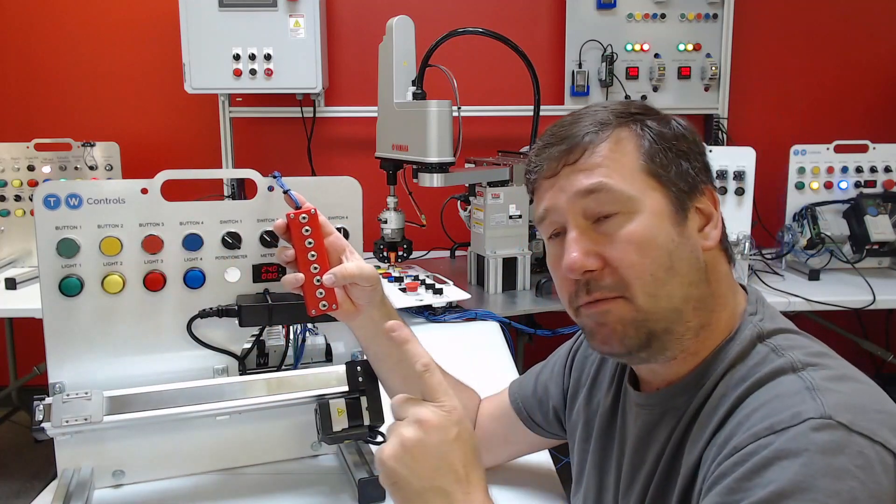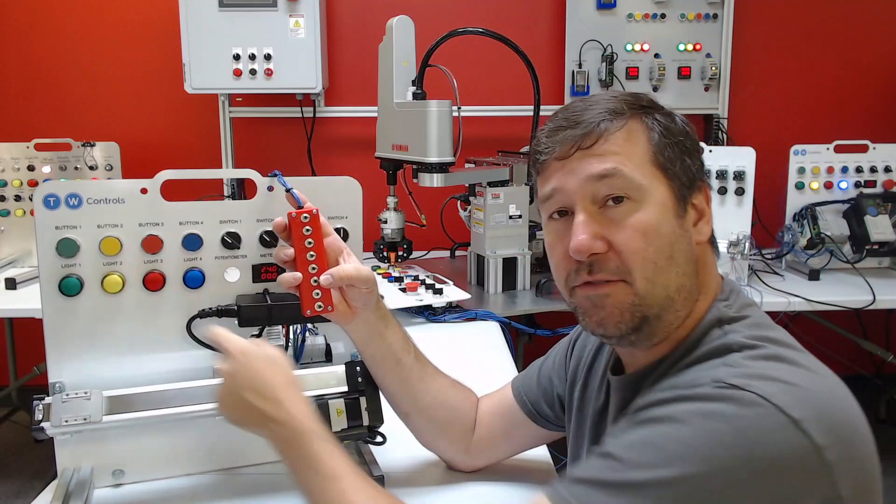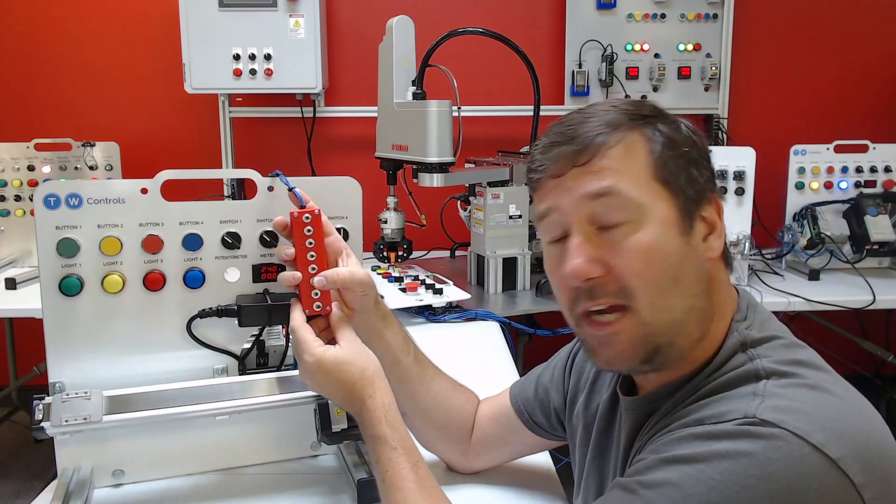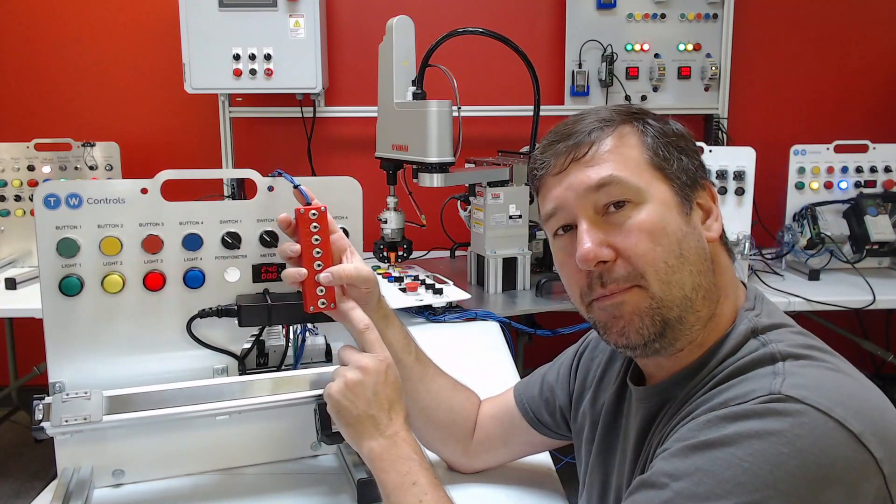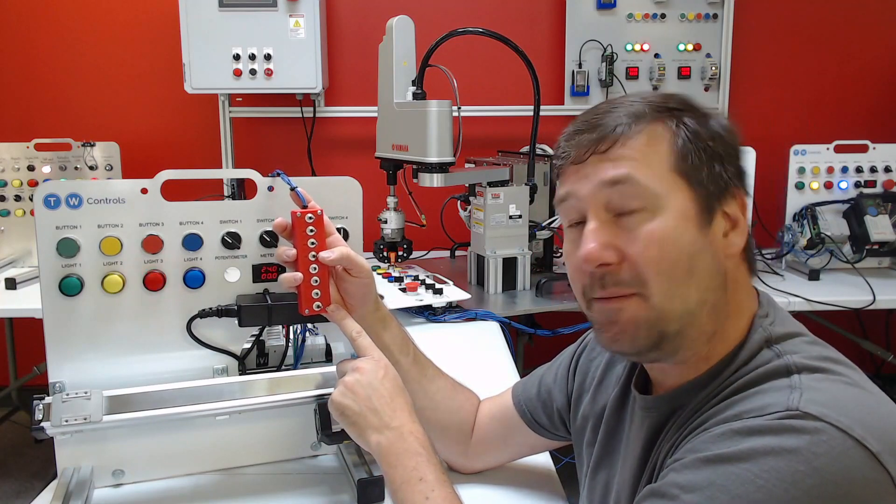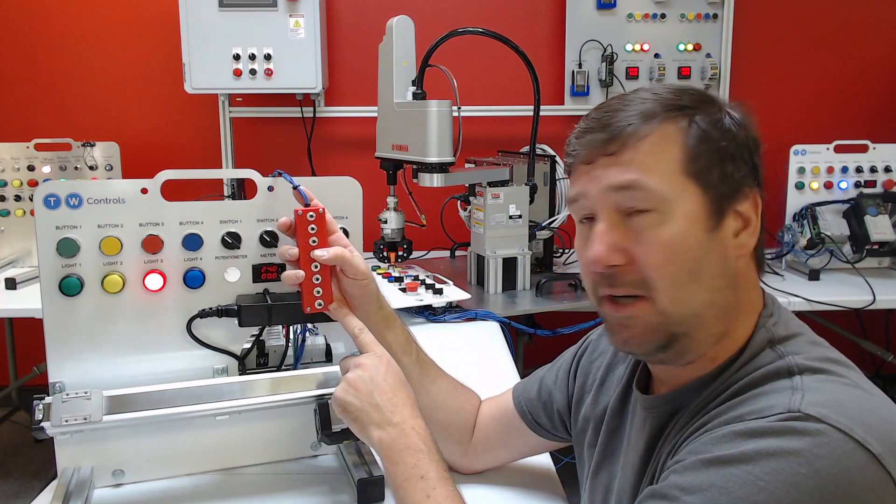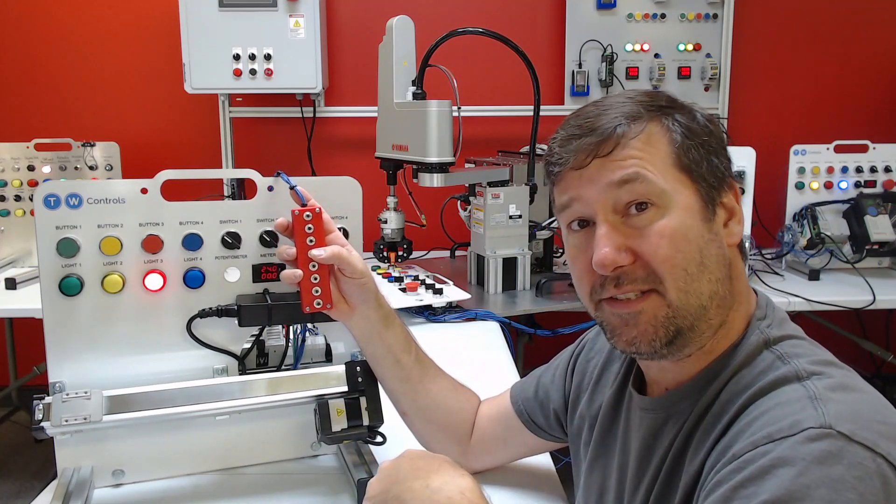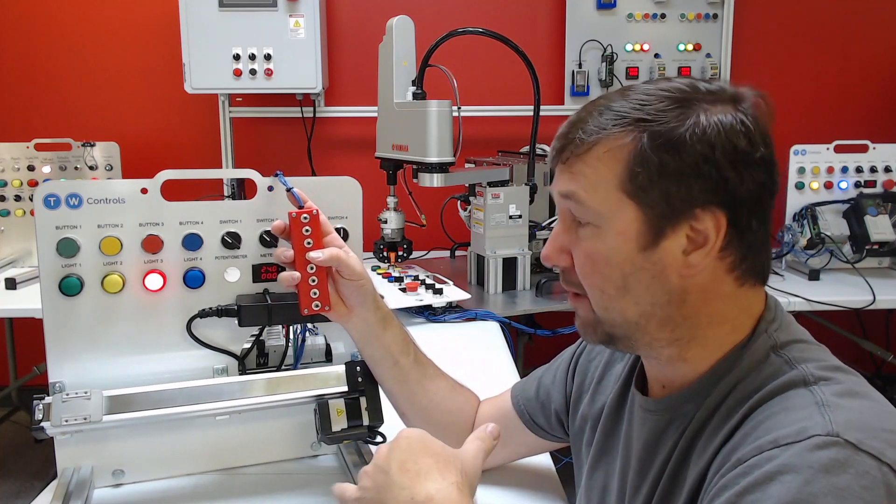But now typically when we hit our lead, one of these two should come on. But it's not going to. Because we want to protect the pump with this. Same with the lag. It's not going to come on. And same with the high. It's not going to come on. That is our kind of fail safe to make sure we don't burn up our very expensive pumps.